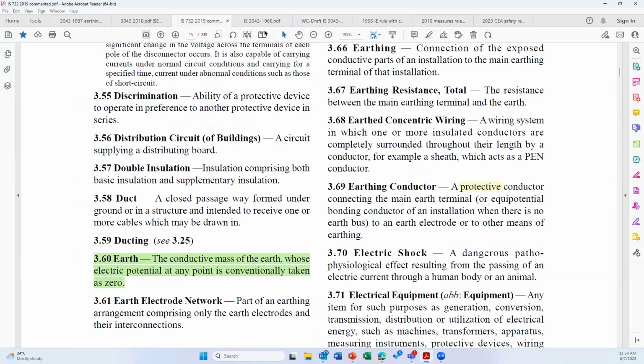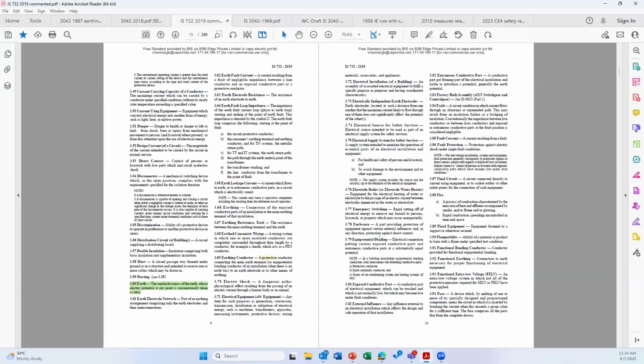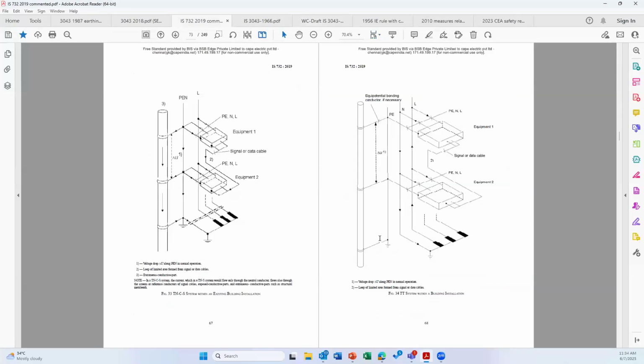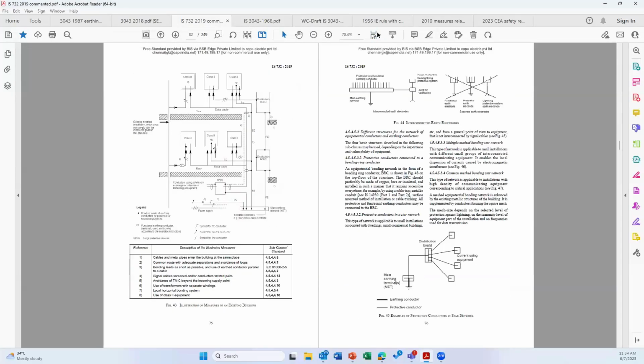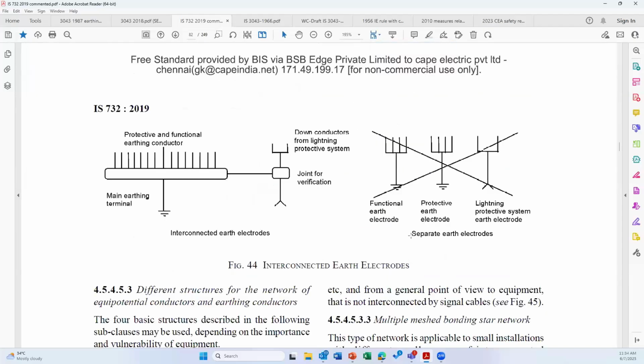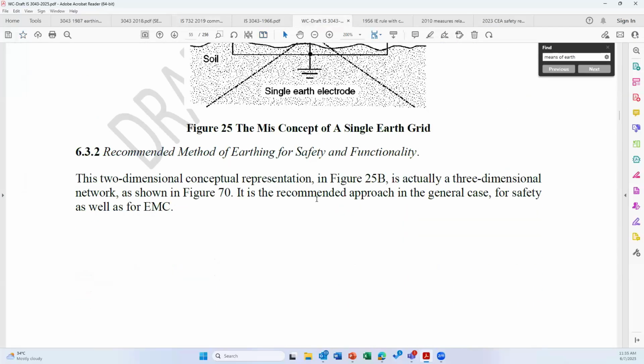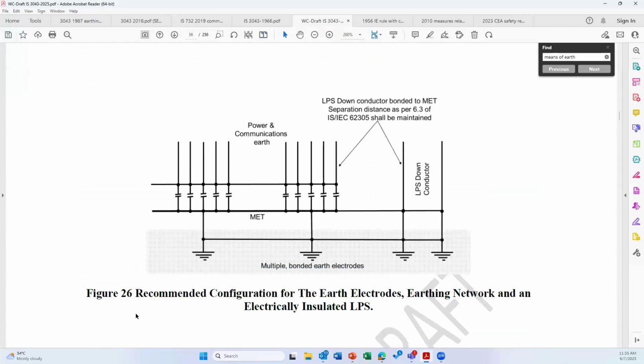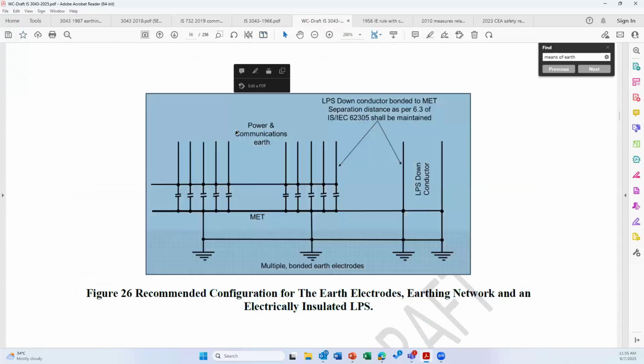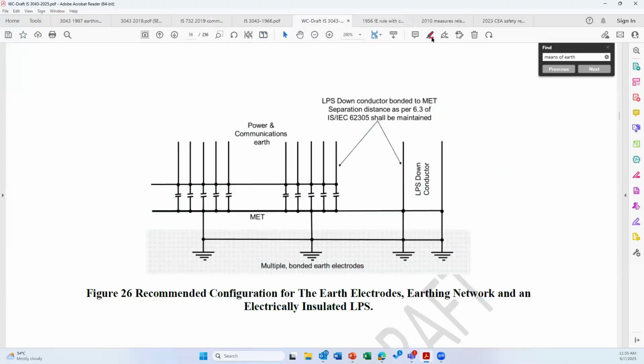These pictures were also there in IS 732. I am taking you to IS 732 2019. Let me scroll down. These pictures were there already in the standard. You can see here a separate earth electrode and a cross mark. So these are not new pictures. These were there for several years, but we were probably not reading them practically. So then what is good? You can go to the next picture. A recommended configuration of earth electrode, earthing network, and an electrically insulated LPS. For example, inside the building, the power and communication, as you can see here, are bonded.